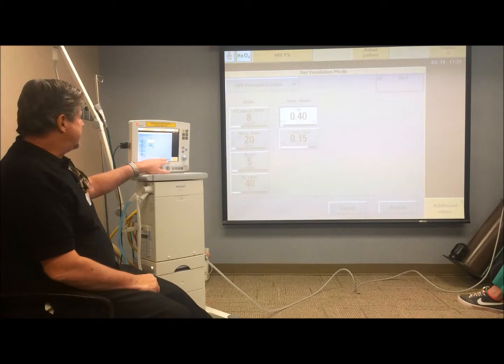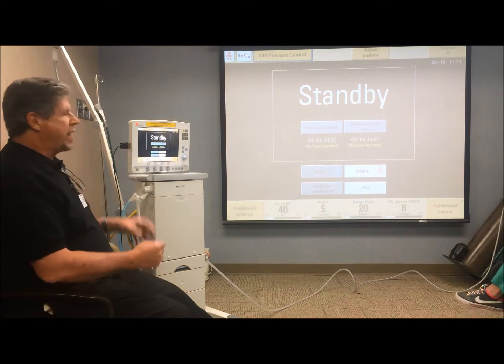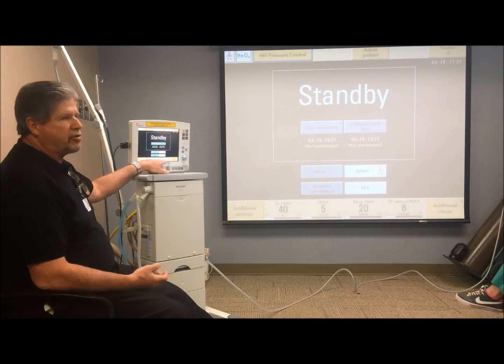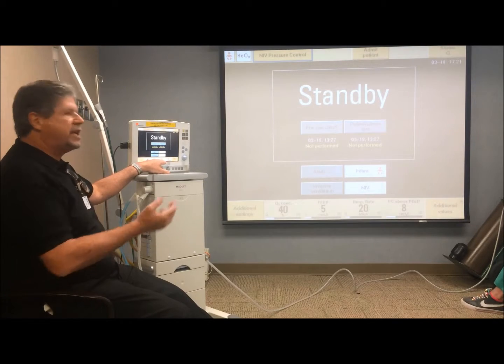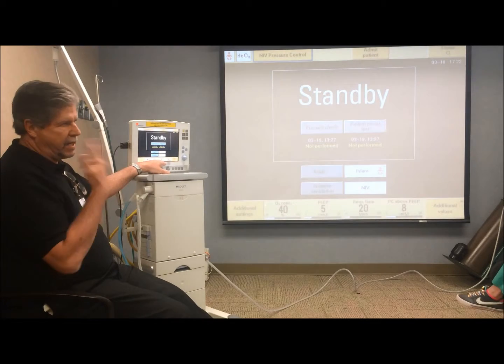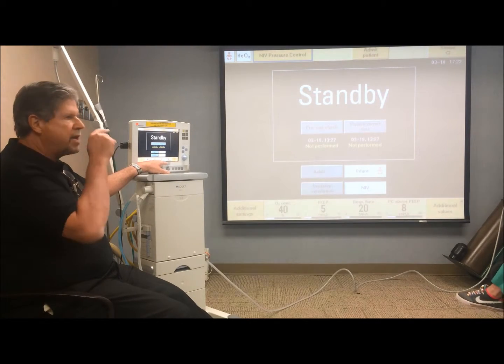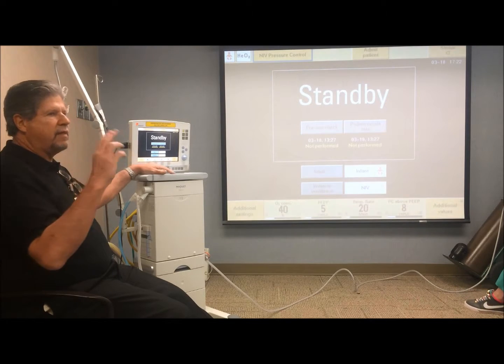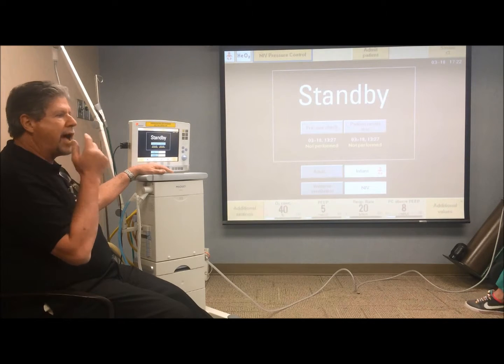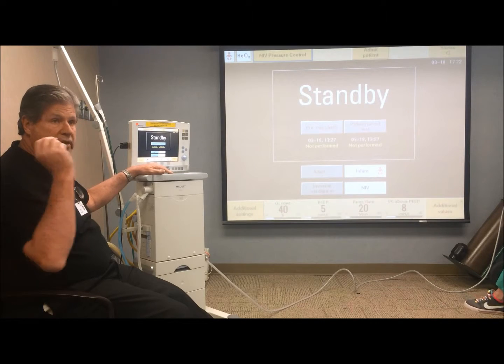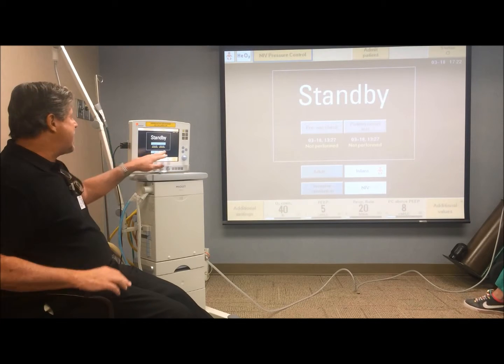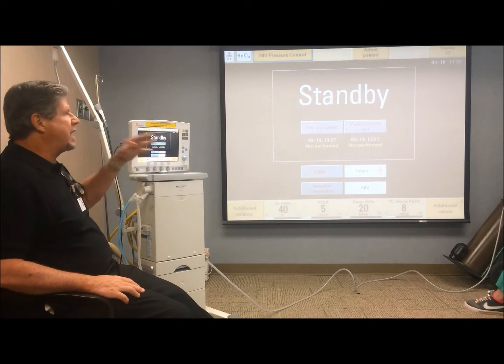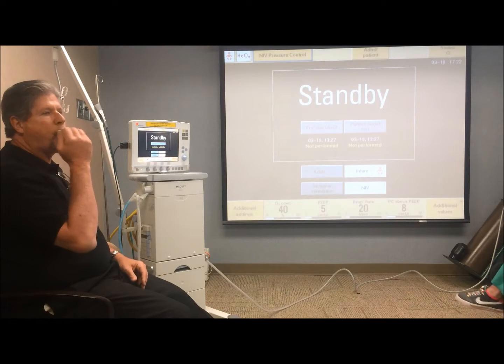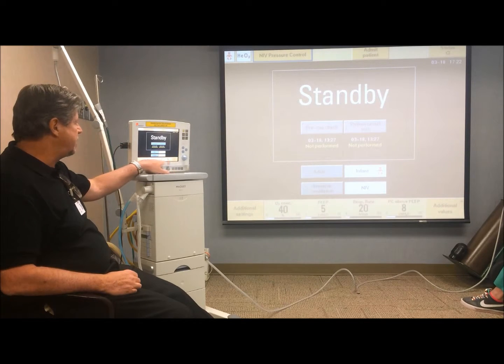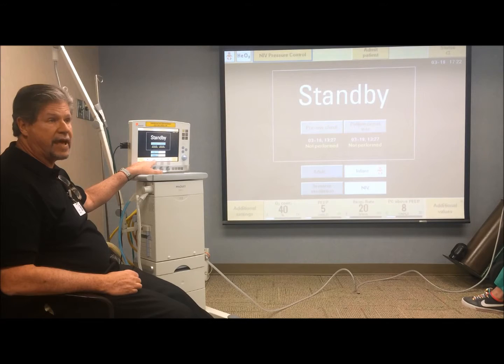Then what happens is that when we're using it this way, the ventilator, because it can't be triggered by the kid, is going to deliver 20 puffs per minute through the prongs. But in between those 20 breaths per minute, there's a leakage flow being applied, because that's how non-invasive works. It applies, if it can't maintain, or depending on the size of the leak, it'll deliver more and more flow to maintain the pressure and PEEP settings that you have.